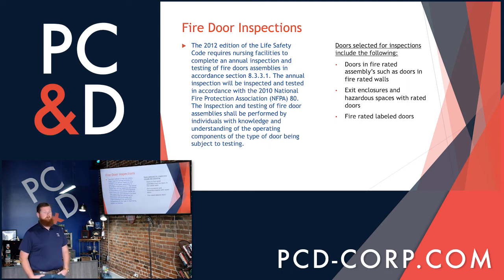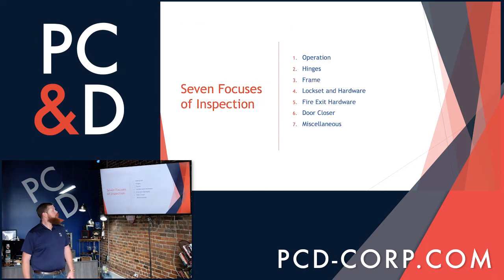Things we will be looking for are delaminated doors, penetrations and holes in doors, physical cracks you can see below, alongside, or on top of the doors, and for positive sealing of the doors to make sure that, again, no smoke or fire can pass through and the rated door can last as long as it's been manufactured to do. Along with the items I've previously mentioned, this next slide will show you in depth the items that we will be looking for as well. As you can see, typical mechanical hardware that would be placed in there, as well as the door itself. With that said, that concludes the inspection portion, and we'll get into PMs.